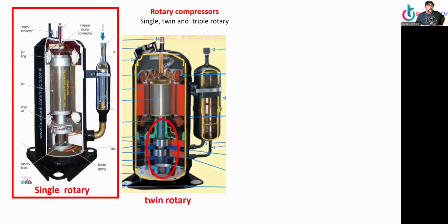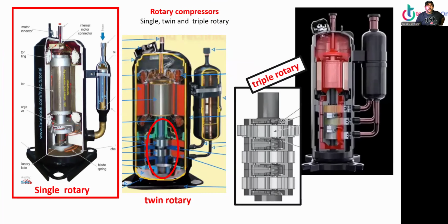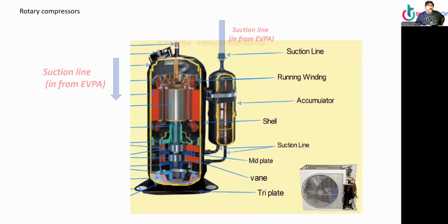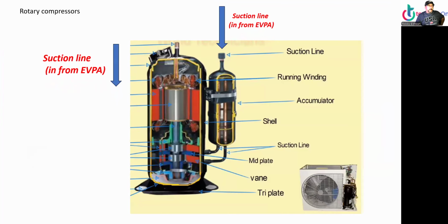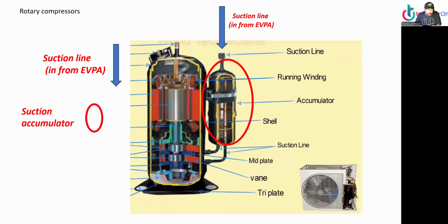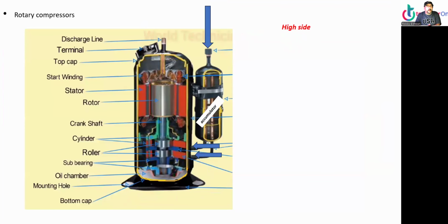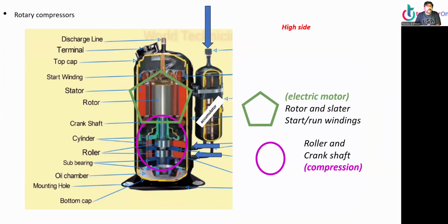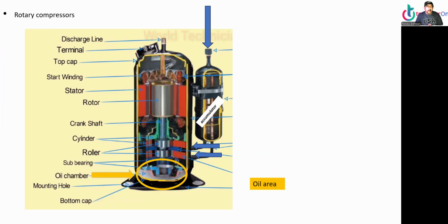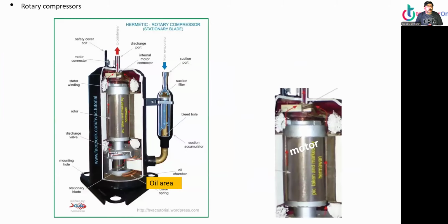Okay, so there's a single rotary. You have the twin rotary. You can see two coming in, and the triple rotary, 1, 2, 3 coming in. All right, rotary compressor. We have suction line in from the evaporator, suction accumulators right there, and this one has dual line in. This is a dual. All right, now the high side. And here is the roller, the crankshaft, the compression area. This is the electric motor, rotor, stator, start and run windings, and discharge to the condenser. So as you can see, the body is high side. And at the bottom is the oil area. Alrighty, and discharge.